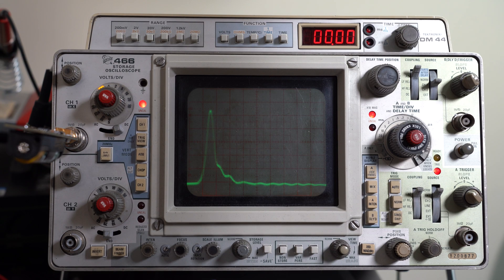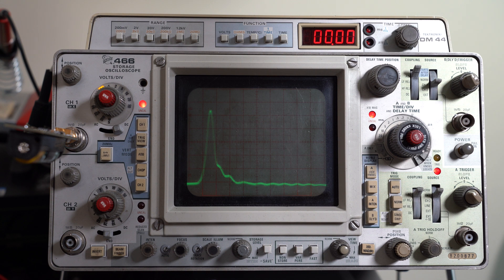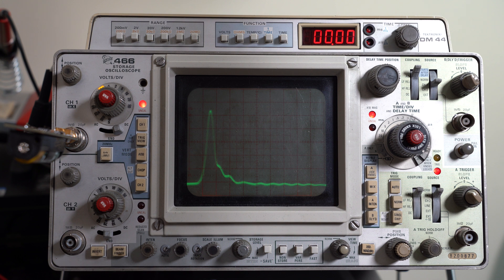On the Tektronix 466 we get a rise time of around 2.5 nanoseconds, which gives us a bandwidth of around 140 megahertz. This is great, once again taking into account the fact that this is a 100 megahertz scope. So once again this being a Tektronix, it exceeds the specifications.